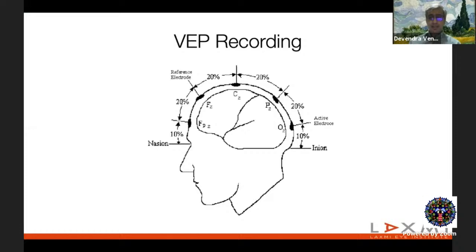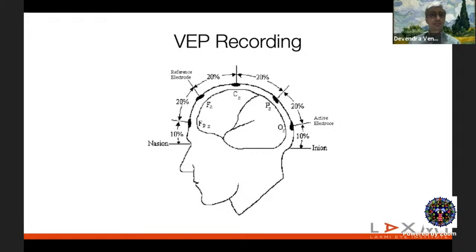Scalp electrodes must be parted through the hair and placed directly on scalp skin. Patients with hair oil should be told to wash their hair with shampoo and avoid oil before the test, as oil prevents good electrode contact.